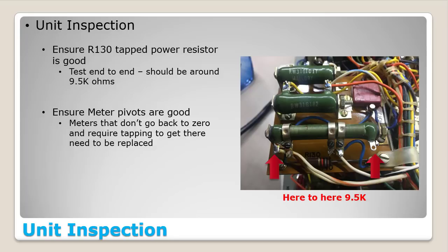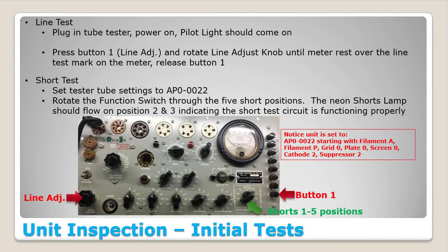And then you want to make sure the meter pivots are good. So flip this thing back over with everything on it, power it on, hit your line test button, and make sure that your meter actually goes back to 0, and you don't have to sit there and tap on it over and over again to get it to go where it needs to go. Okay, assuming all is good up to that point, then you can keep moving forward. If not, you need to address the things you found.